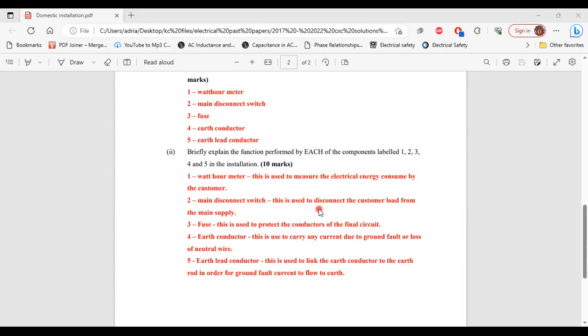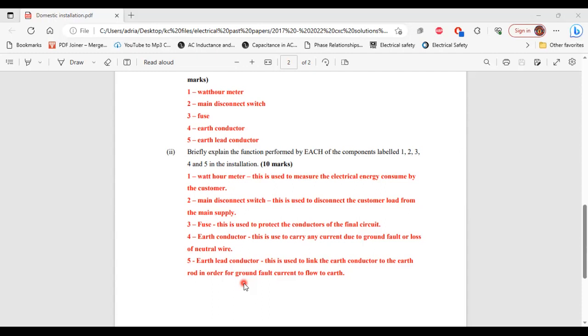Three, the fuse: it is used to protect the conductors of the final circuit. Number four, the earth conductor: this is used to carry any current due to ground fault or loss of neutral wire. Number five, the earth lead conductor: this is used to link the earth conductors to the earth rod in order for ground fault current to flow to earth.